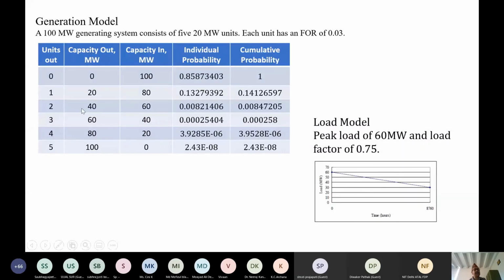And you can see again, you can construct this type of table. This type of table is also known as a capacity outage probability table. It shows the capacity outage with individual probability. You can see 0 capacity will be outage with this probability. 20 megawatt capacity will be outage with this probability. 40 megawatt will be outage with this probability. 60 with this probability, 80 with this, and 100 with this probability.